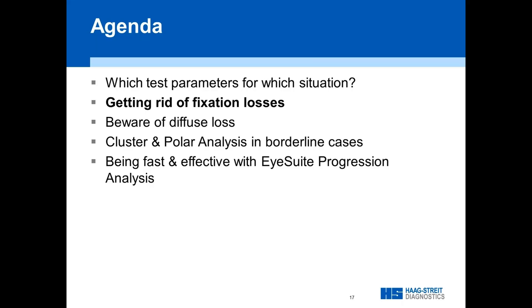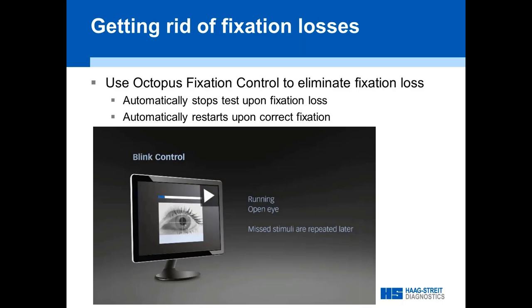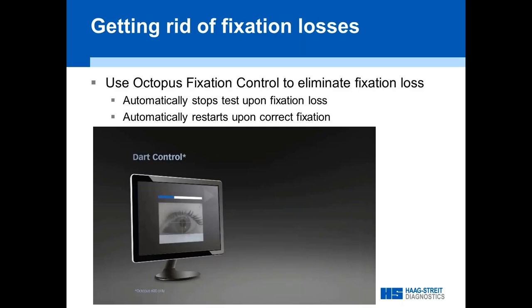Something really unique and helpful about the Octopus is that you can get rid of fixation losses. Fixation losses typically happen when patients look somewhere else because they don't see a stimulus and get worried they're doing something wrong. What the Octopus does is track the pupil. The software notices if somebody closes an eye or looks away and automatically pauses the test. The moment the patient fixates properly again with eyes open, it just restarts — so you're not losing much time and each point is tested reliably.